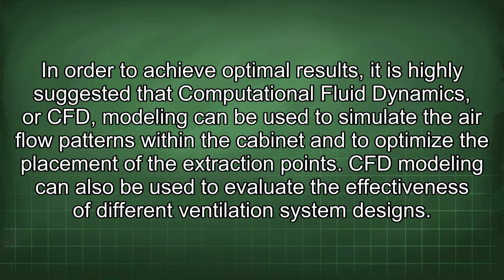In order to achieve optimal results, it is highly suggested that computational fluid dynamics, or CFD, modeling be used to simulate the airflow patterns within the cabinet and to optimize the placement of the extraction points. CFD modeling can also be used to evaluate the effectiveness of different ventilation system designs.